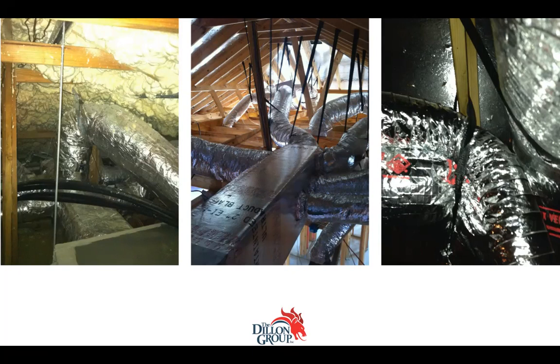And I know the lawyers are getting involved because I've been working for some of them, trying to figure out what the most likely cause is. And I had one guy working for the opposition. It was a big engineering firm. And he said that the duct system in this house was the best sealed he'd ever seen. And I said, that's interesting, because you can't actually see how well the duct system was sealed, because all you looked at was the insulation. The sealing is supposed to take place on the inside where I looked. Here's what you get. Yeah. That's a quick way to win a case.